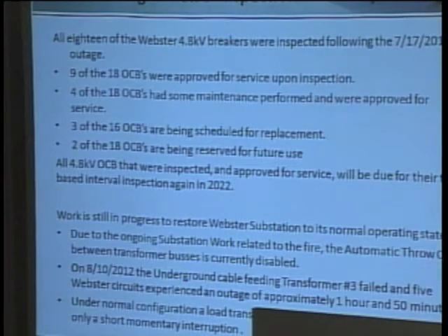Work is still in progress to restore Webster. The portable substation is still at Webster, but the diesel generators have all been removed and the circuits have been restored to working order. And then there was another outage at Webster which affected two circuits in Berkley. I should state before that three of the 13 circuits at Webster feed directly into Berkley, and those were the areas that had most of the outages, approximately the northeast corner of the city, Woodward and 12 and a half mile area.